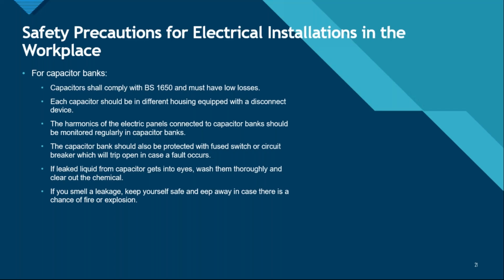The harmonics of the electrical panels connected to capacitor banks should be monitored regularly. The capacitor bank should also be protected with a fuse switch or circuit breaker, which will trip open in case a fault occurs. Capacitors basically run on chemicals. In case there is a chemical leakage and leaked liquid gets into your eyes, there is a different first aid procedure for cleaning the chemical from your eyes. Wash your eyes thoroughly and clear out the chemical. Also be careful that the chemical in your eye does not run from one eye to the other.